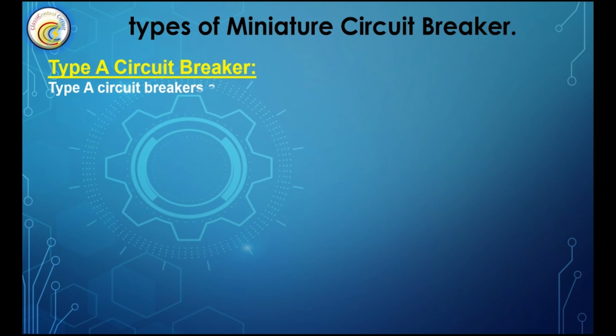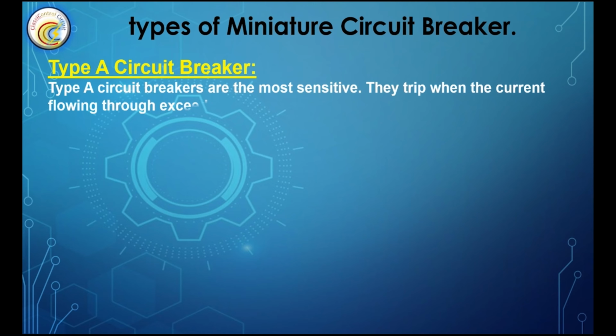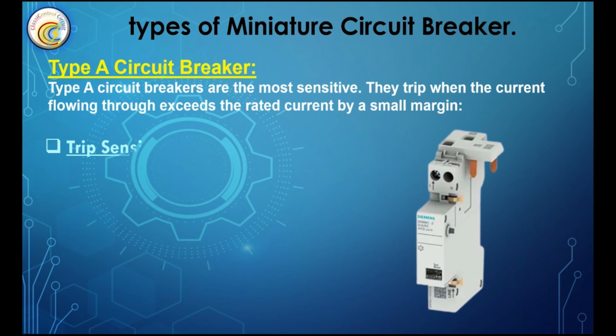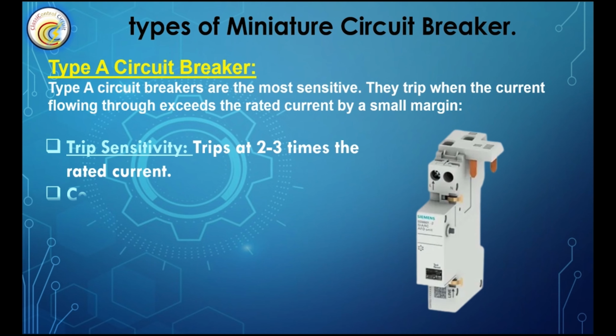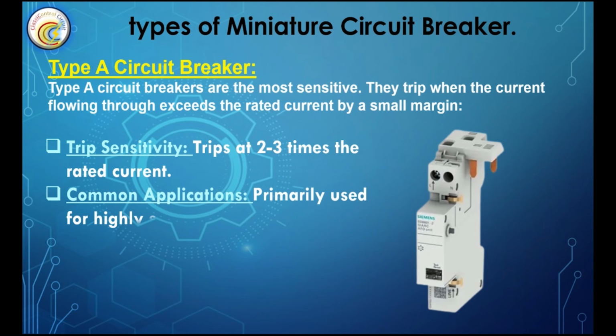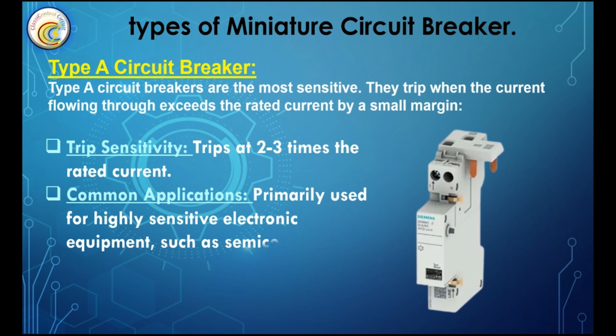Type A circuit breaker. Type A circuit breakers are the most sensitive. They trip when the current flowing through exceeds the rated current by a small margin. Trip sensitivity: trips at 2 to 3 times the rated current. Common applications: primarily used for highly sensitive electronic equipment, such as semiconductors, and circuits with long cable lengths where voltage drops can be a concern.